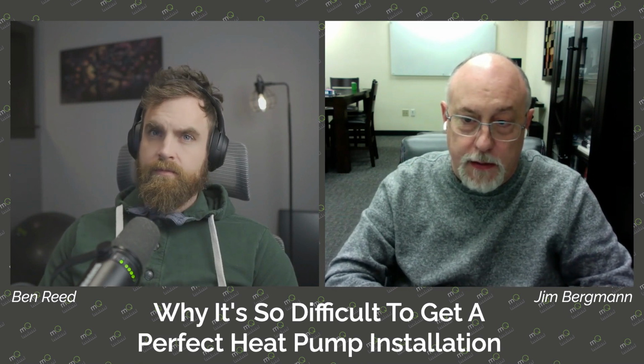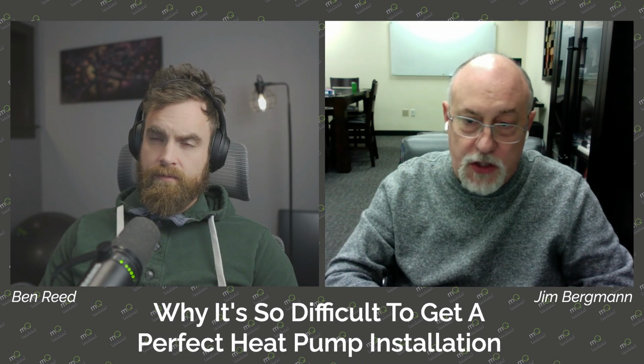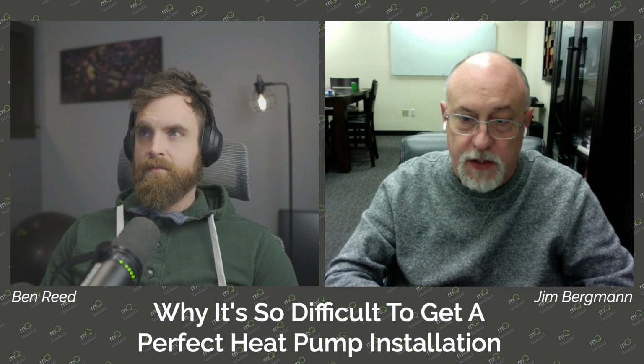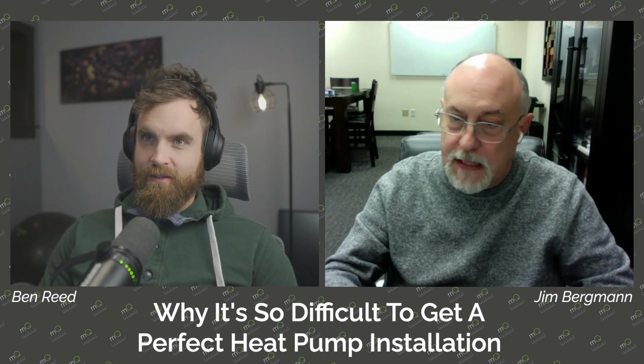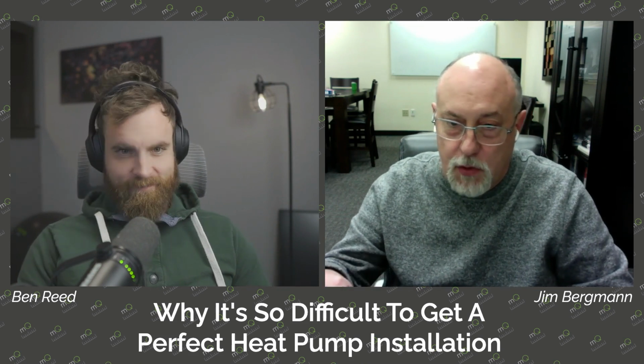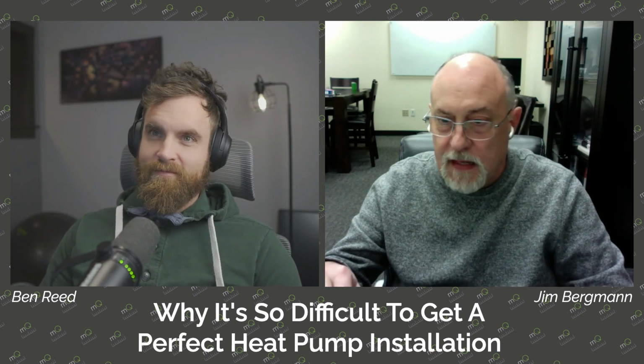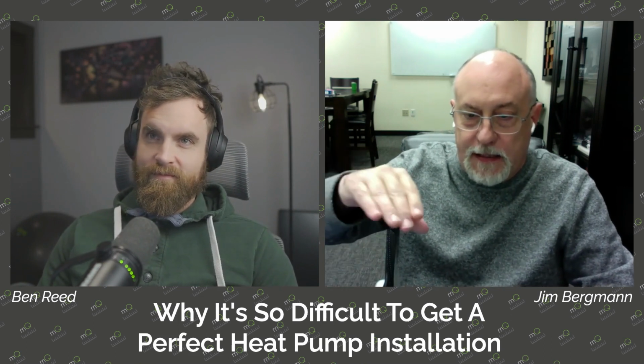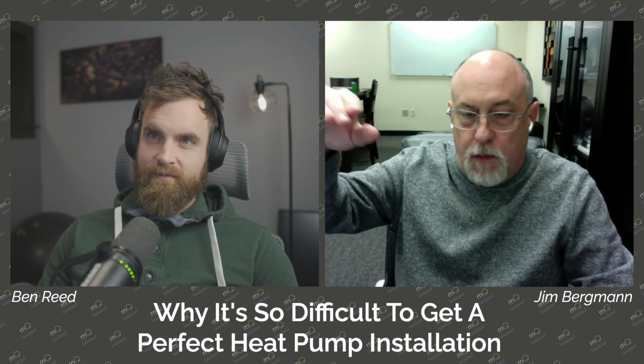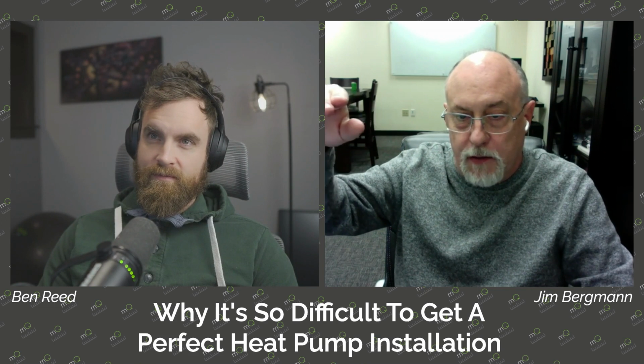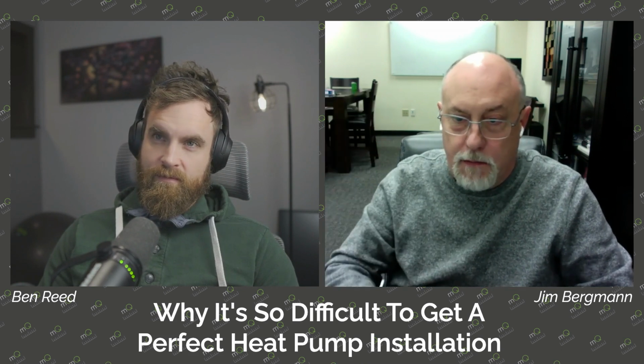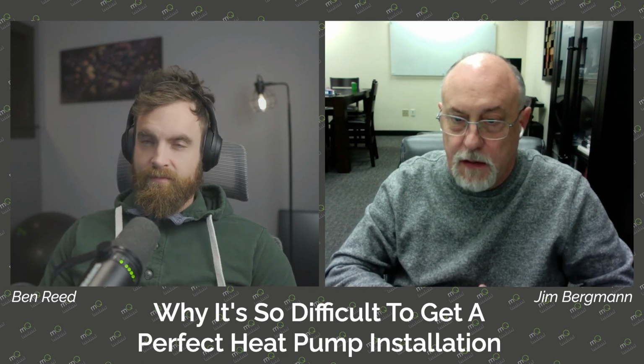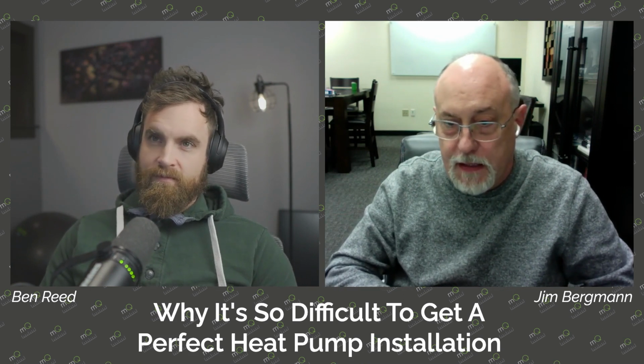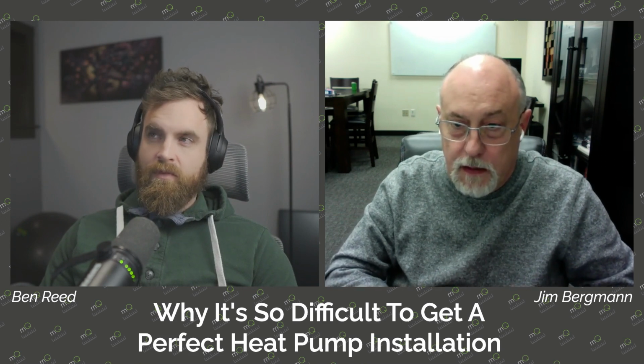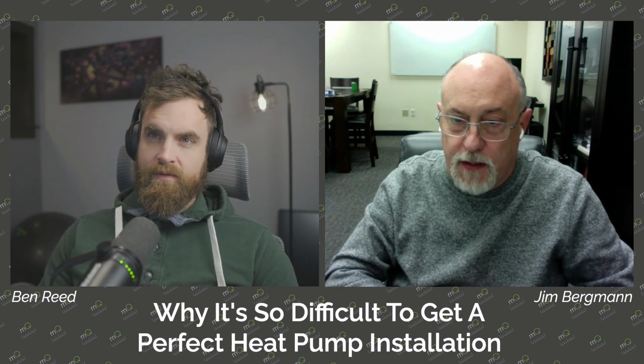This is where I can watch my subcooling, right? So on a heat pump, again, we're still watching subcooling, but now it's the subcooling coming out of the indoor coil instead of out of the outdoor condenser on the air conditioning system. So I'm watching a lot of things happening at once. I might start off with no subcooling, which means I got no liquid coming out of my coil. As I'm adding gas, I start to see the subcooling increasing, and I see my BTUs increasing, and I see my amp draw going up. When I see my amp draw go up on my heat pump and I see no increase in output, then I know I've peaked out on how much refrigerant's in that thing. We're trying to catch it before we hit that peak point, because once we cross the peak, we're going downhill, right? Ideally, we get enough refrigerant in that we get enough capacity.